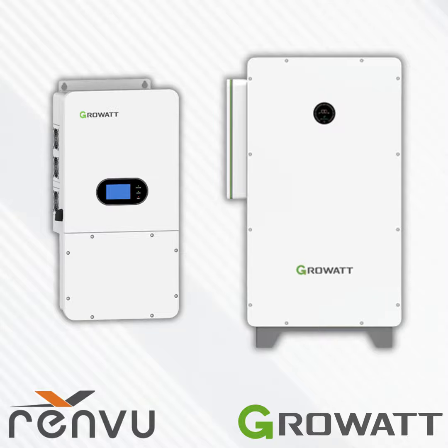This is the WIT and APX system that we offer. On the left is the APX. It's a modular lithium iron phosphate battery. Each module is 14 kilowatt hours, and the product ranges from 86 to 200 kilowatt hours when stacked. There is a single BMS that controls both stacks. So you can do one stack or two, as long as you're within those constraints of 86 to 200 kilowatt hours.